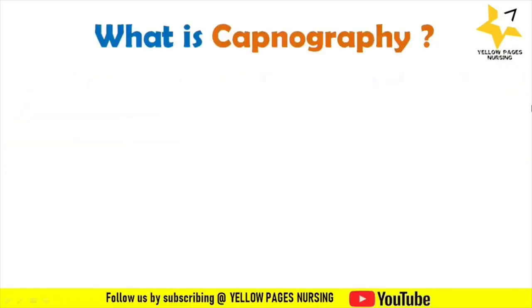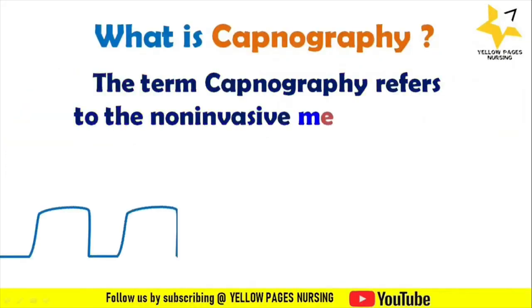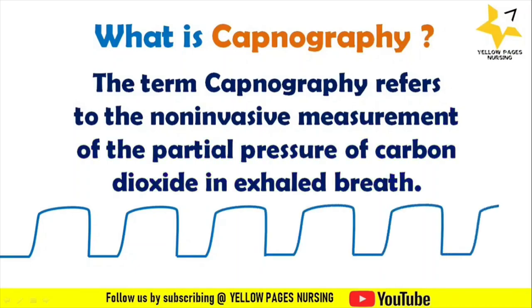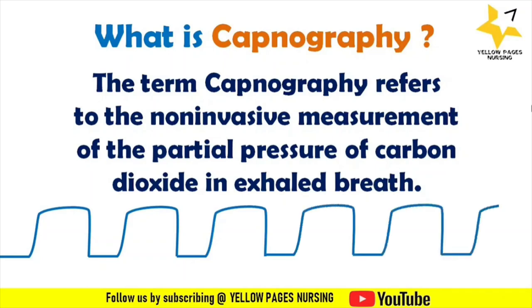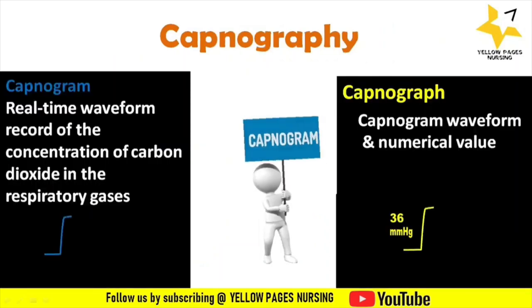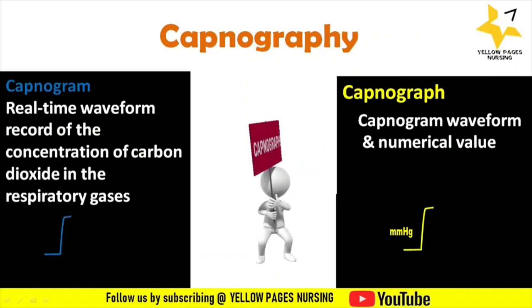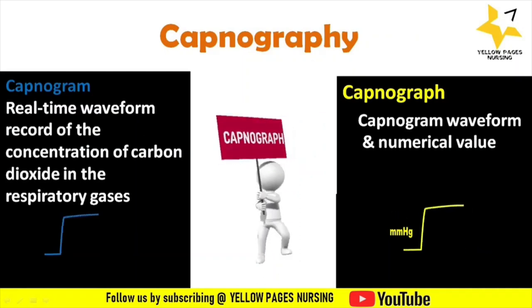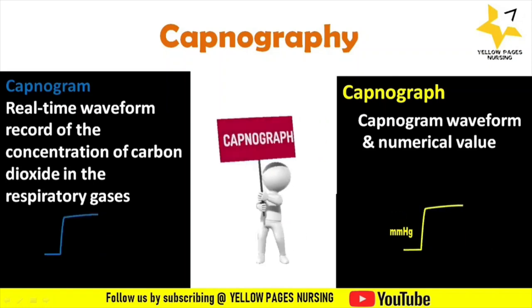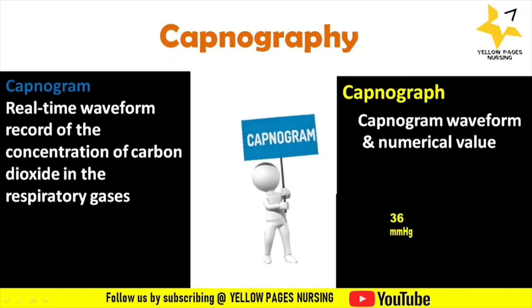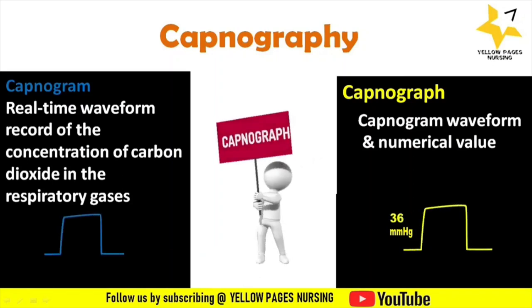What is capnography? The term capnography refers to the non-invasive measurement of the partial pressure of carbon dioxide in exhaled breath. It provides a breath-by-breath analysis and a continuous recording of ventilatory status. Capnogram provides a real-time waveform record of the concentration of carbon dioxide in the respiratory gases, whereas capnograph provides waveform plus numerical value.